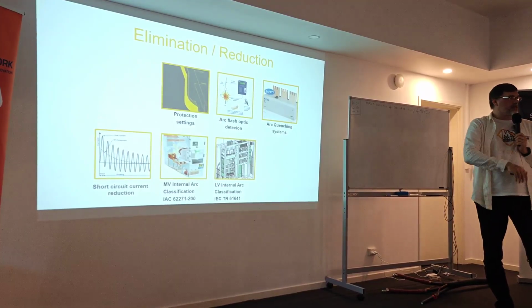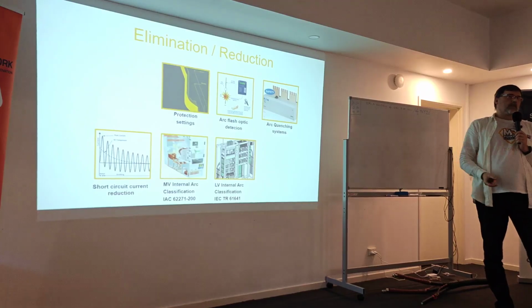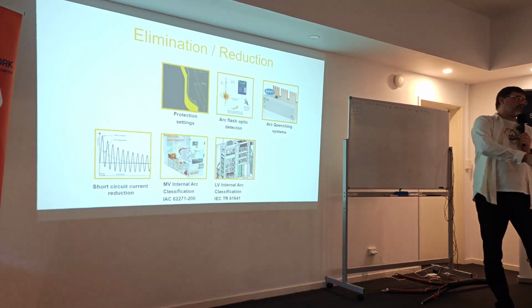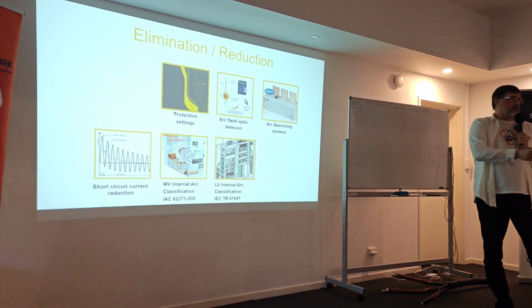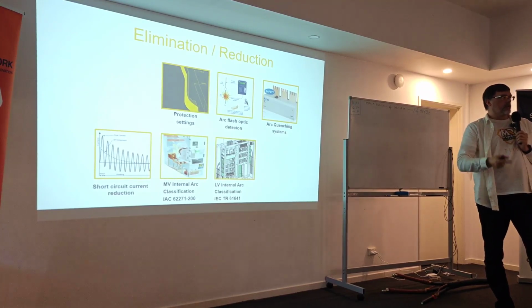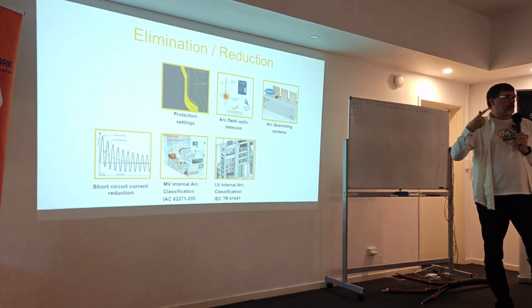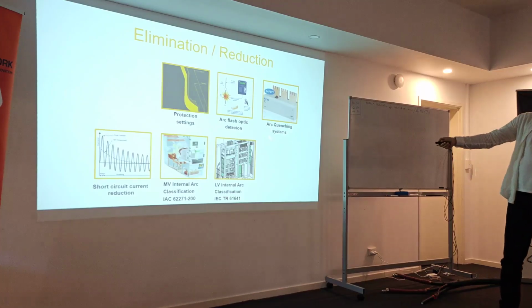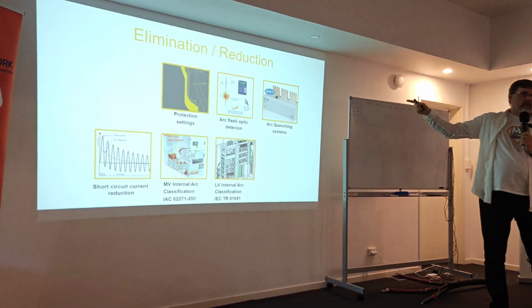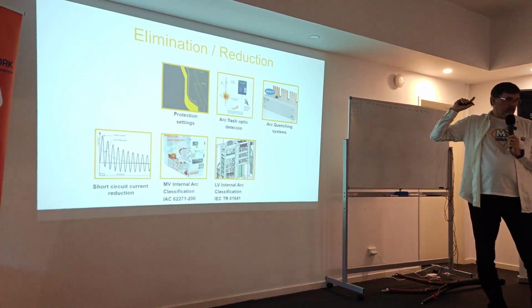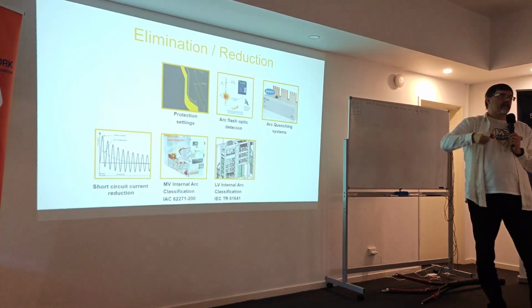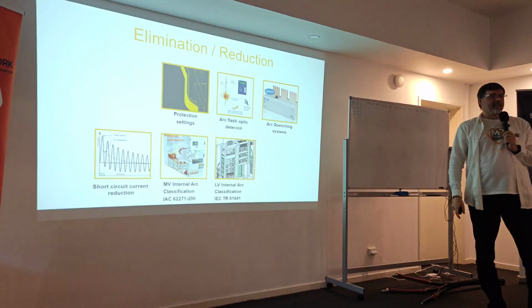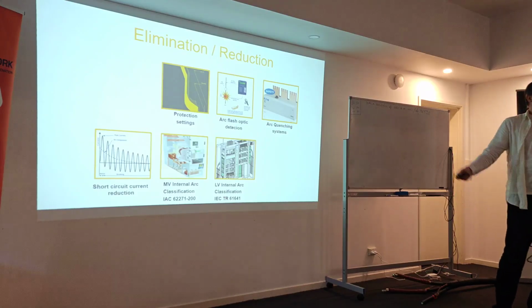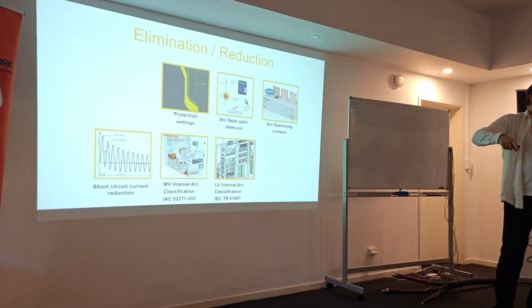Flash optic detection, something that David already mentioned, can be a standalone system, or relays can have it. There is a discussion whether it is better to have a standalone, separate system that does this, or the relay, because of the computing power of the relay itself. The arc quenching system, that's the Arcteq thing, and there are actually three companies doing them. David said Schneider is doing. Schneider is not doing. They don't have anything, they are buying, but Arcteq is doing for Siemens and for themselves.